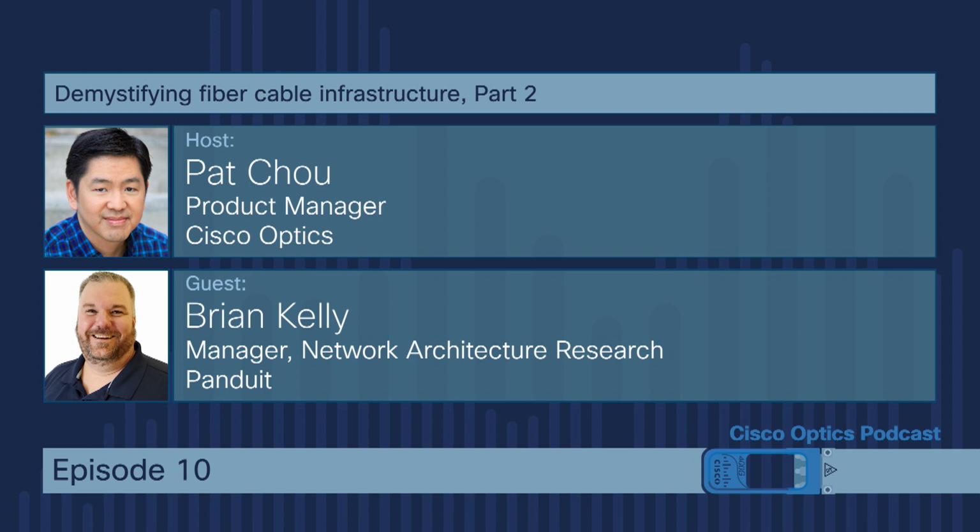But you could also buy transceivers and then plug in a patch cord in between those. Say you put an SFP transceiver into the server, connect in a fiber patch cord, say an LC patch cord, run it up to the switch, plug the SFP transceiver into the switch, and then an LC connection into that transceiver. You could do that as well. So there are really three ways you could do it in a normal data center these days.